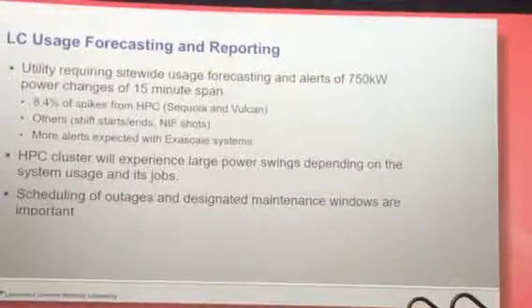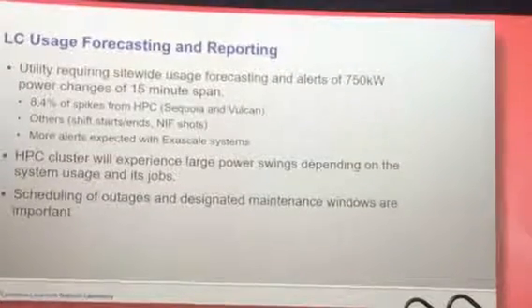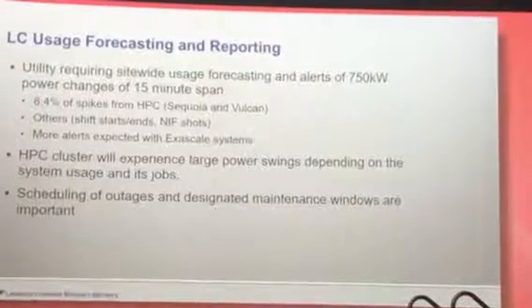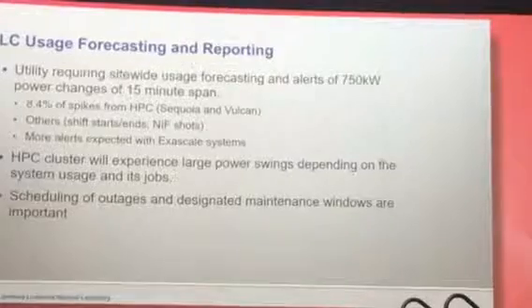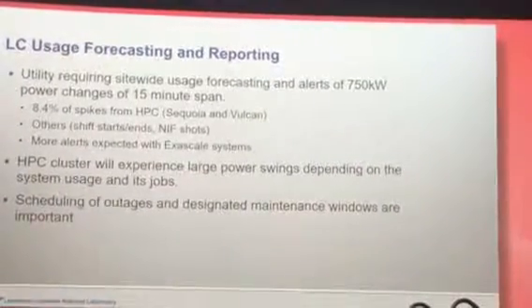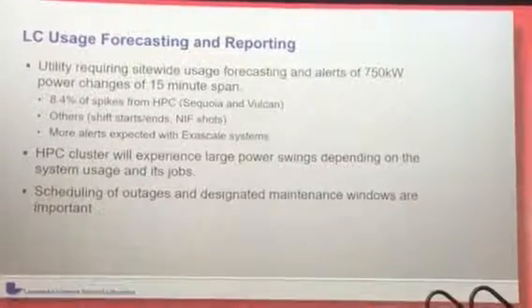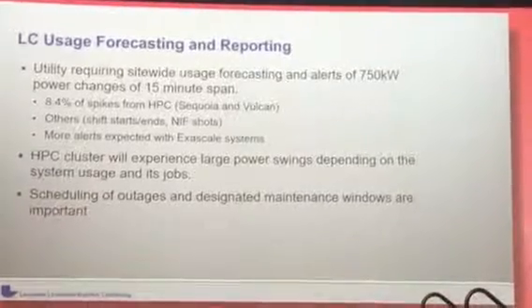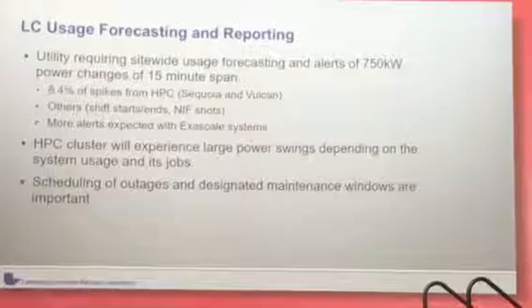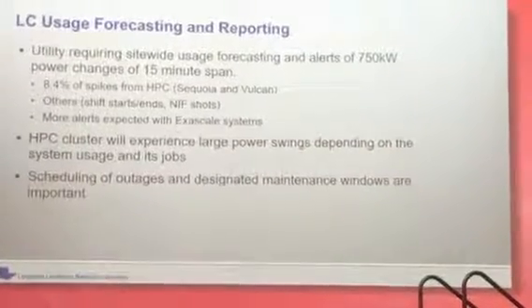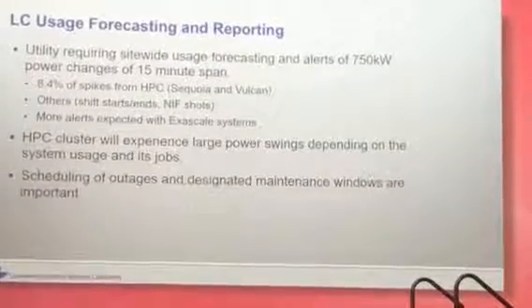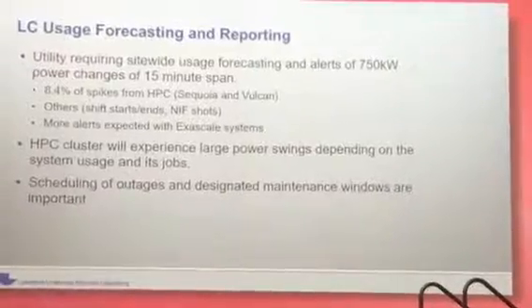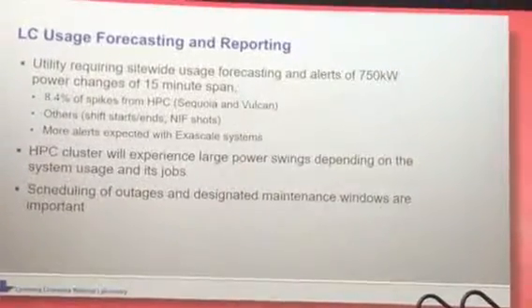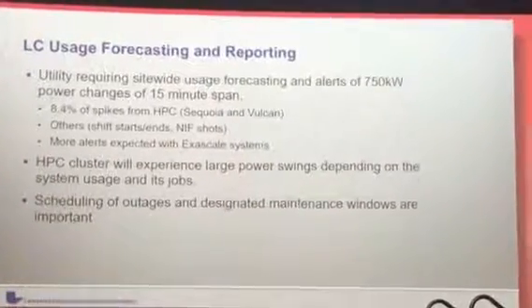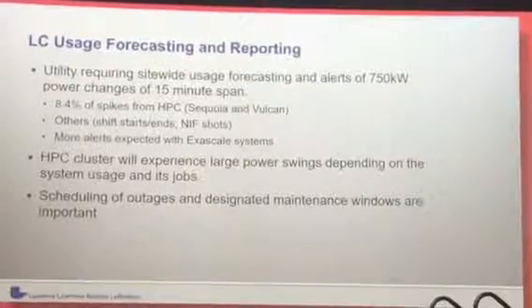So with these huge block loads, forecasting and reporting is important. Our utility company requested that whenever we have a 750 kilowatt swing over a 15-minute span, we report to them, just so they can make sure they have that amount of power available to supply to us, or if we're not using the power, to sell it back to the market. Over a 3-year span, we had about 1,400 alarms or alerts, and 8.4% of those were due to just the high-performance computer, either ramping up for certain runs or just powering down. So when exascale computing comes in about 2021, we're expecting huge swings of power. So that's something that we have to start getting into. And then also notifying the utility that we're doing maintenance on a system so they can plan for that power change.